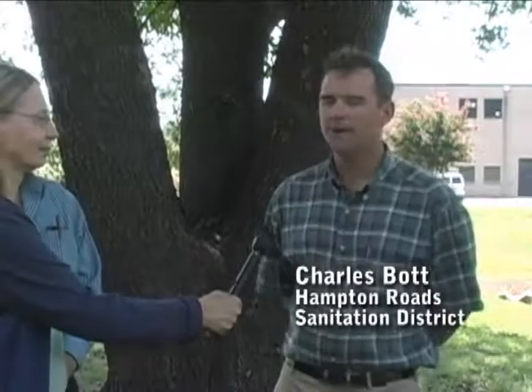I'm here with the advisory committee members from the siloxane project. We at HRSD have had several digester gas to electricity projects in the past, and some of those have not worked out well, primarily as a result of poor gas quality and the need for better gas treatment. We're now designing about a 2 megawatt facility at one of our treatment plants, our Atlantic plant, and we're hoping very much to use what we've learned from this project about gas treatment to guide the design and the media selection for siloxane and hydrogen sulfide removal.